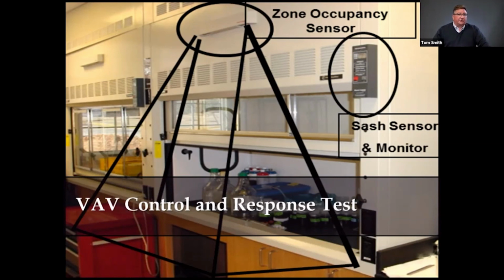So now we move toward the VAV control and response test. Now there are many different ways for variable volume systems to modulate flow. And it's important now in today's modern systems that we move beyond this measurement of face velocity. Because measurement of face velocity tells us the flow through the hood when the sash is open. But what happens when the sash is closed? How low a flow can we tolerate before we lose containment, or we create an unsafe situation inside the hood?